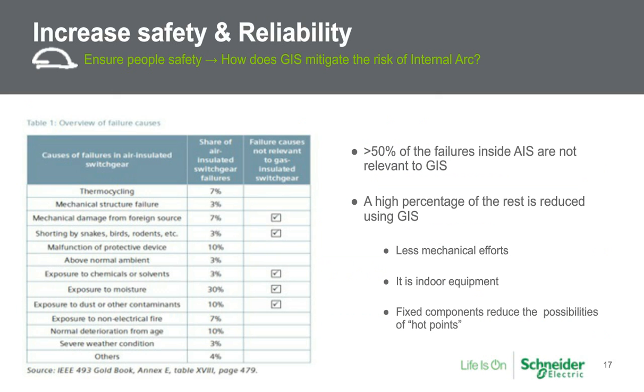So this is a really good slide. I really want to share it with everybody and focus on this one for a minute. This is talking about a study from the IEEE Gold Book, and it showed the share of air-insulated switchgear failures and the main causes of that. It went through everything from abnormal operating conditions to mechanical damage from a foreign source, that being either someone doing maintenance or some other cause of mechanical damage, all the way down. And with gas-insulated switchgear, we can say that over 50% of these common failures in air-insulated switchgear are not relevant to GIS.